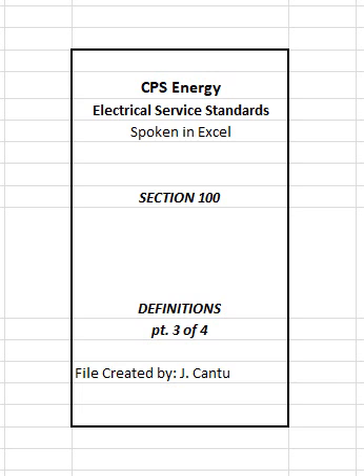B. Board areas and apartment complexes with underground service. On 1 meter installations, the point of delivery will be at the load side of the meter socket or load side of the metering current transformers. Where a main disconnecting device is installed ahead of meters, the point of delivery will be on the line side of the main disconnect device. Customer shall provide cable terminating lugs appropriate for cable size.